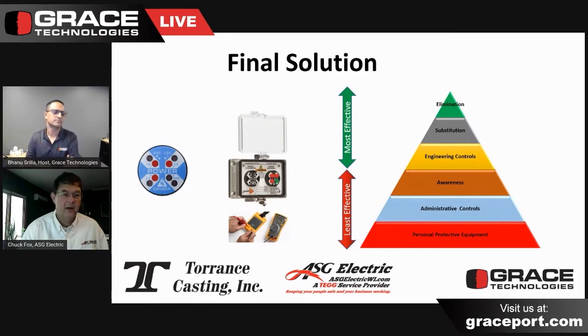Right. The other advantage of the voltage indicator is that it will display what I refer to as an always-on available voltage. So if for some reason they lose an entire phase, they could see that condition right off the voltage indicator on the display of the control cabinet with this installed.